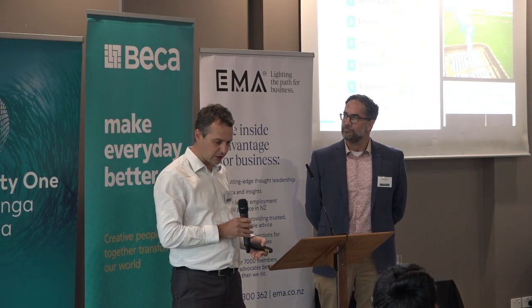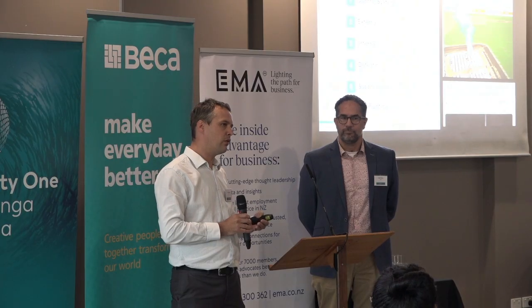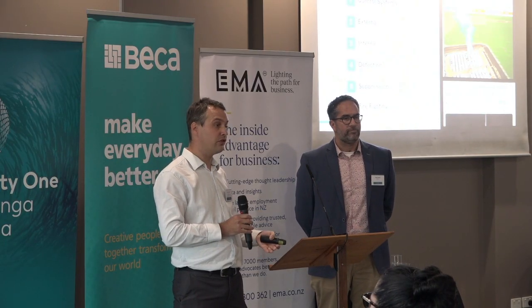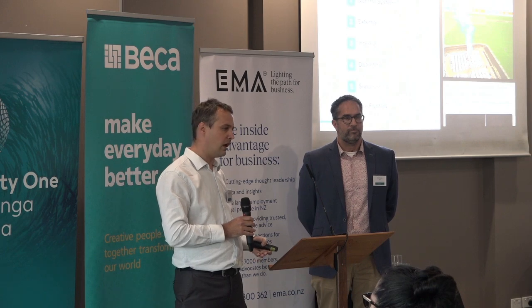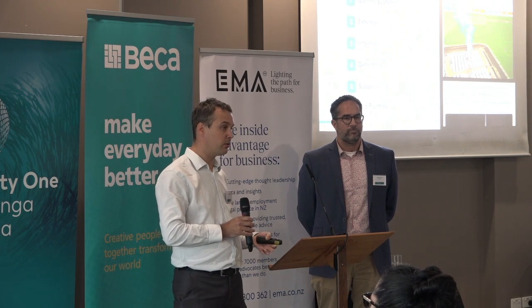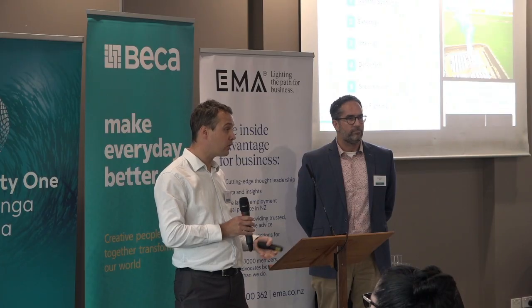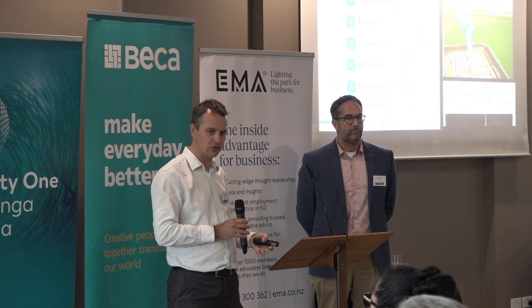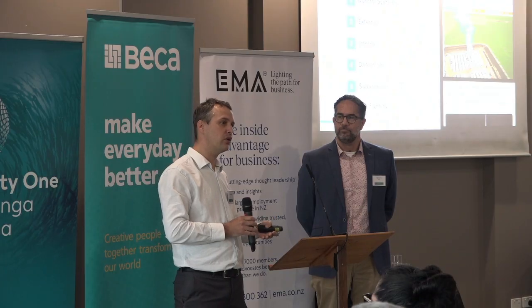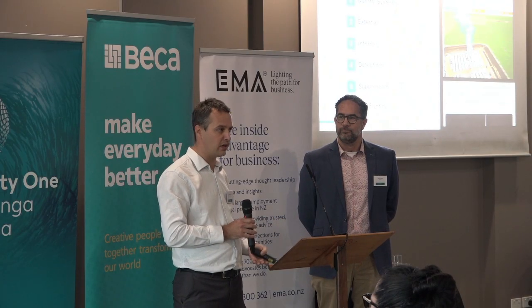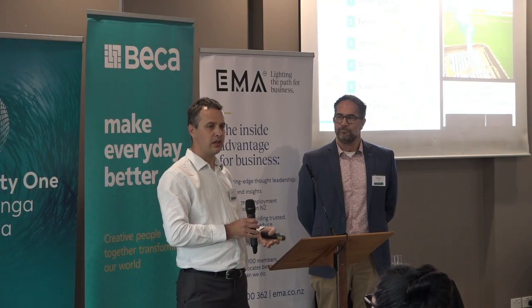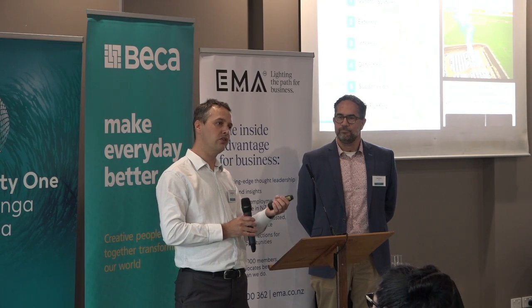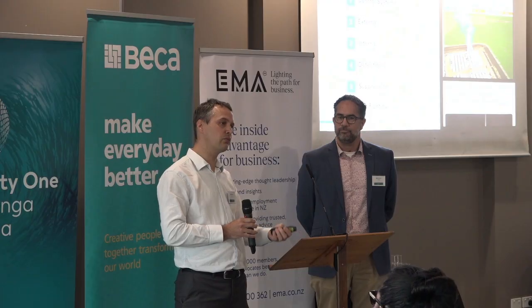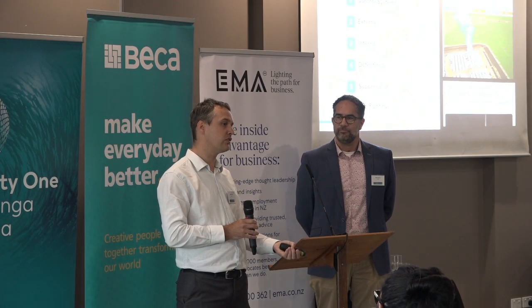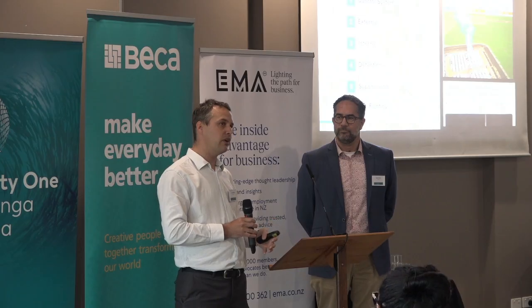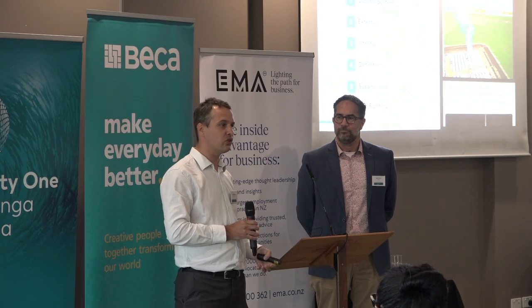In terms of fire safety systems, we see a lot of these going to market more and more now - specialist battery fire detection systems. Many of you in the industrial space will be familiar with things like VESDAs, or aspirating smoke detection, a very expensive version of a smoke detector. Some of those are being tuned to deal with battery off-gassing now. There's some merit in that - it gives you early warning. But once your batteries have started to fail and release those gases, it's probably entering that thermal runaway process. I'm yet to see whether that allows you to actually stop and save that battery.